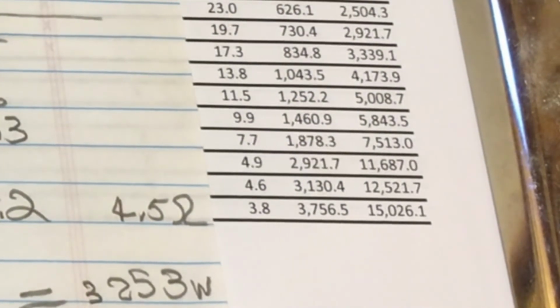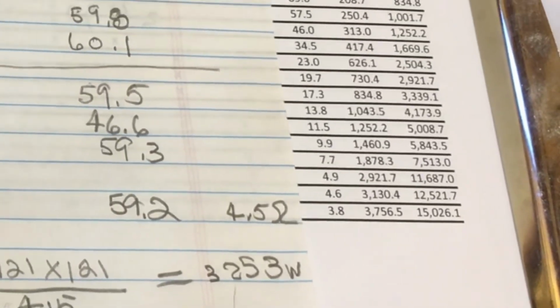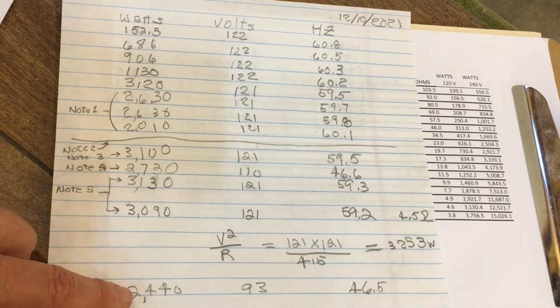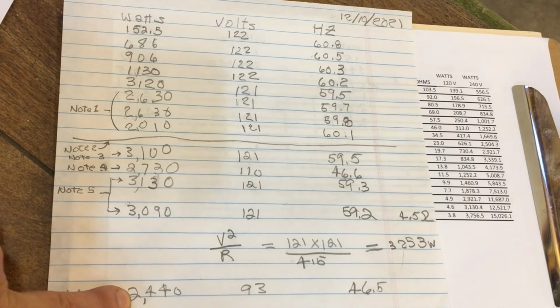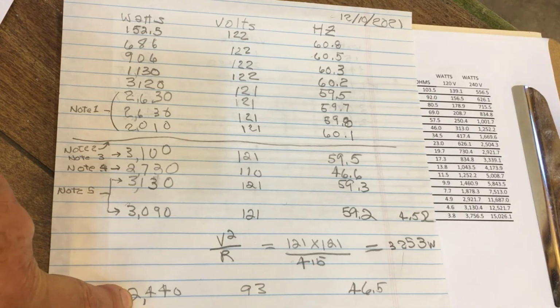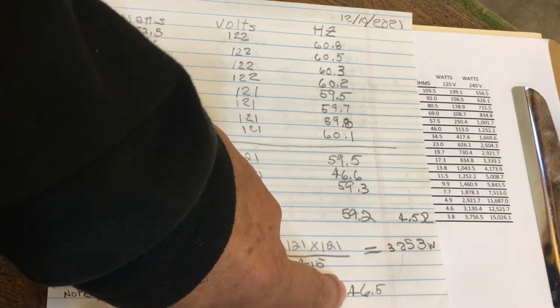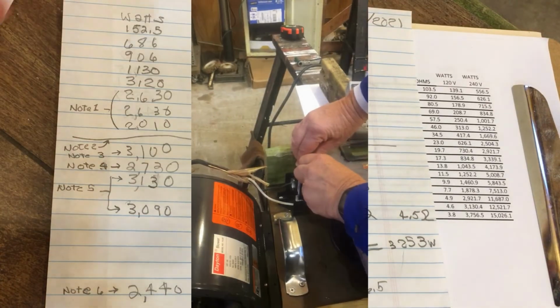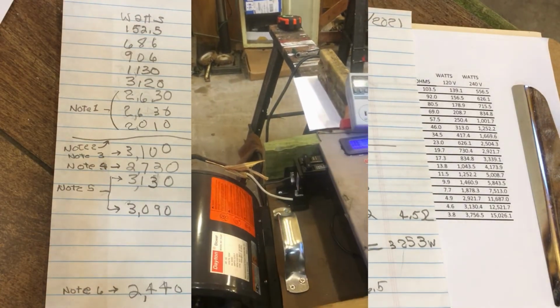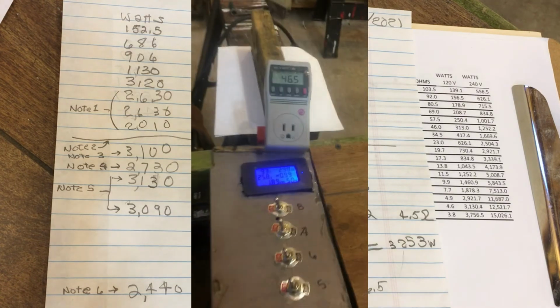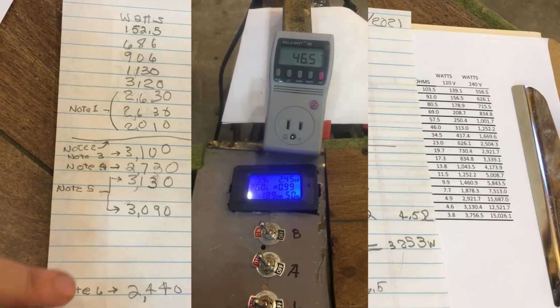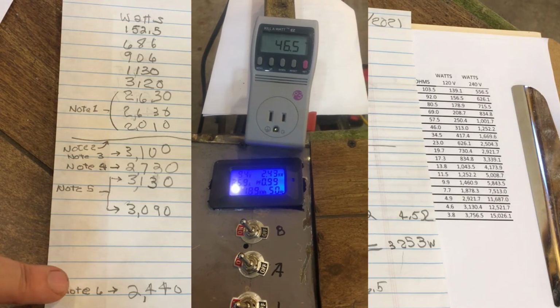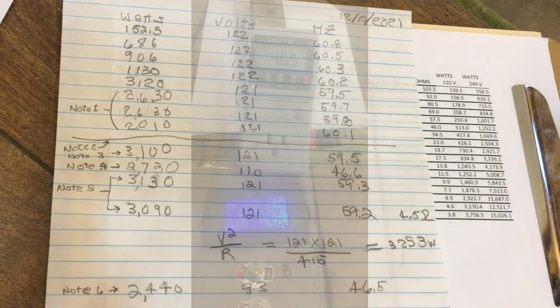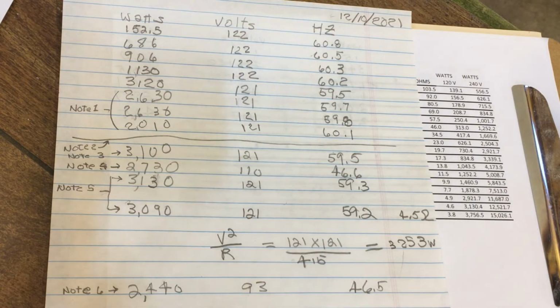But what happened was, when I put the minimum resistance on here, instead of increasing the load, it went down to 2440, and the voltage fell to 93. And the frequency was down to 46.5. So the unit stayed online. By that I mean the engine kept on running, but it was really struggling and knocking along, and it was way past its ability to carry loads. So again, 3,100 seems to be about the maximum load that it can carry dependably.